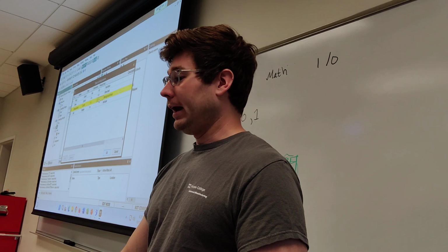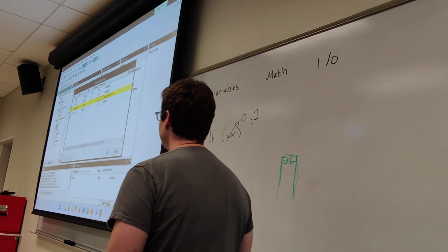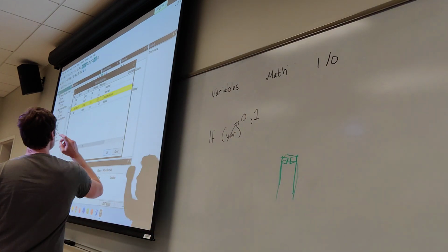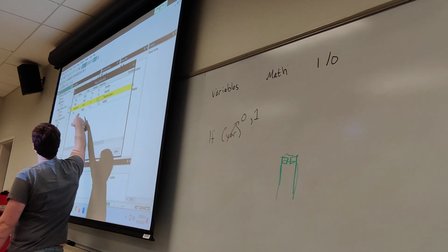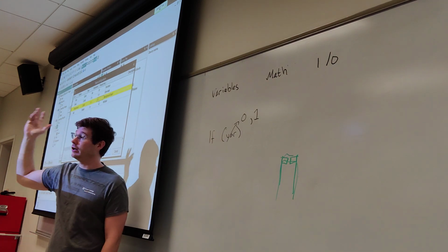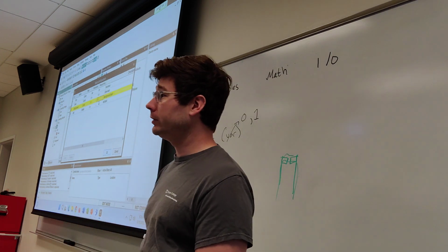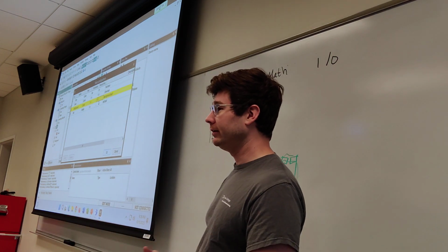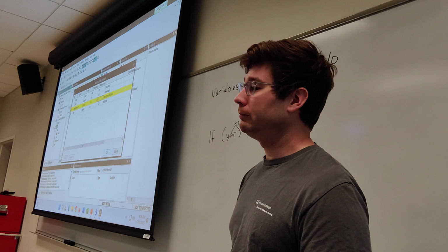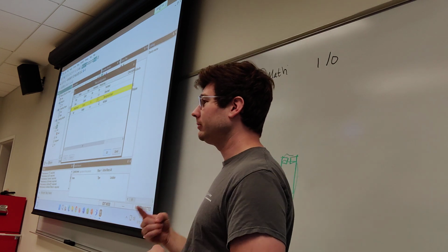Background runs at 500 milliseconds, right? See, the unit is milliseconds. So every half of a second, this task will run. Okay, it's not very often at all. Typically, this is a task that moves really, really slowly, right? Something that doesn't change very quickly. Maybe some math that doesn't have to be crunched very often.